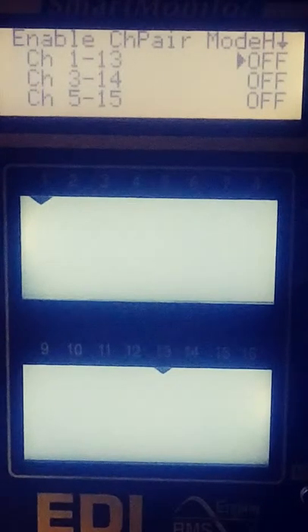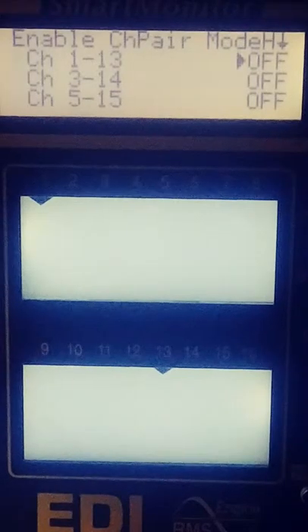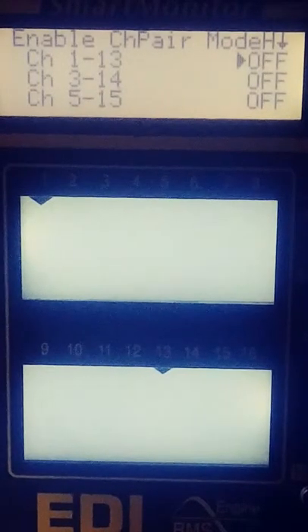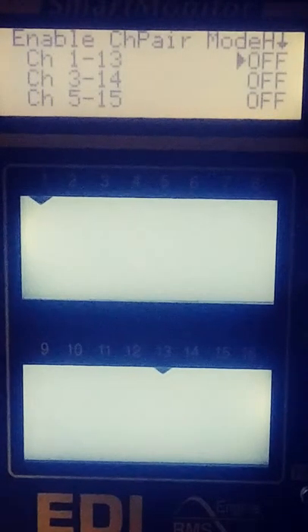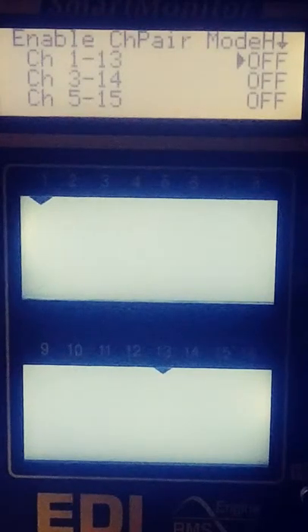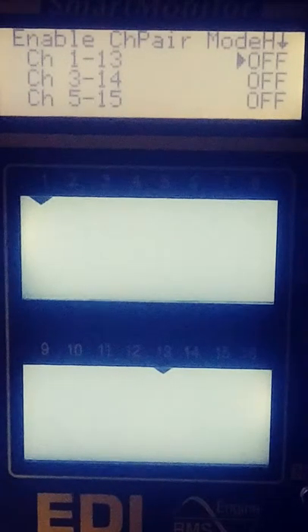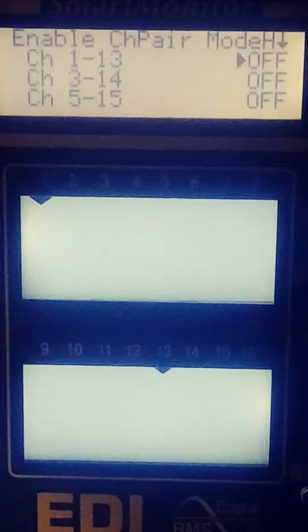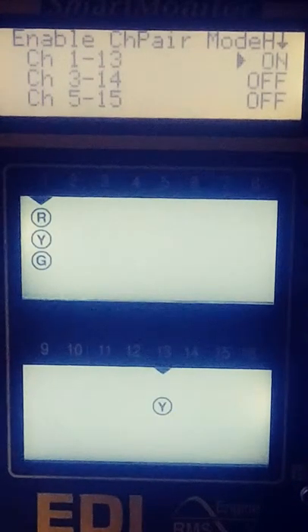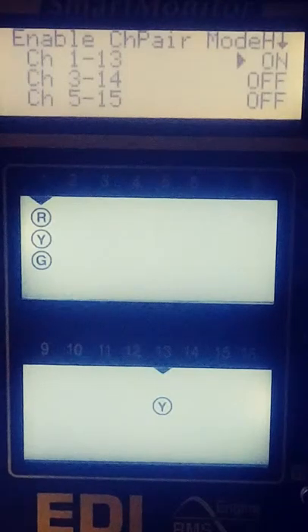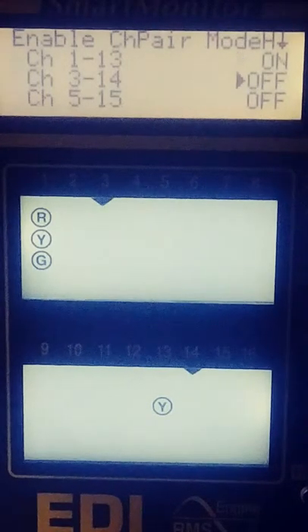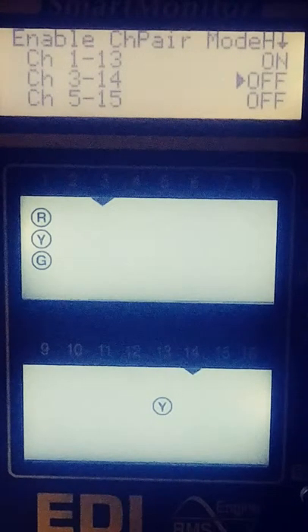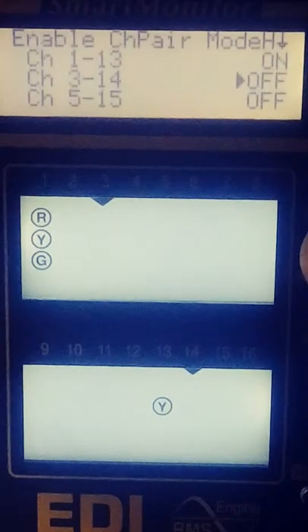Now in this screen you want to actually structure what type of flashing yellow arrow phases you need enabled. If you only have two phases, for example one and five, you want to turn one and five on. For the purpose of this video though I'm going to act as if all four phases are being enabled.